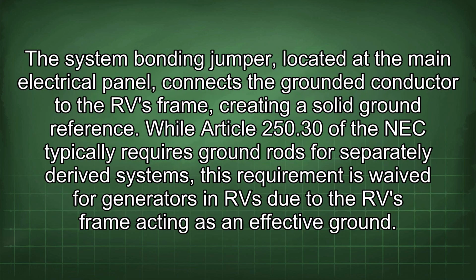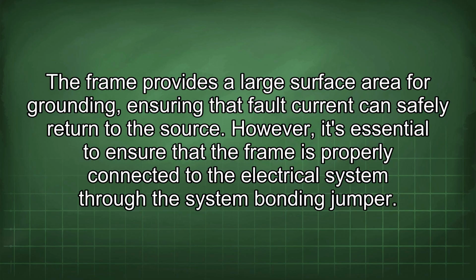The system bonding jumper, located at the main electrical panel, connects the grounded conductor to the RV frame, creating a solid ground reference. While Article 250.30 of the NEC typically requires ground rods for separately derived systems, this requirement is waived for generators in RVs due to the RV frame acting as an effective ground. The frame provides a large surface area for grounding, ensuring that fault current can safely return to the source. However, it's essential to ensure that the frame is properly connected to the electrical system through the system bonding jumper.